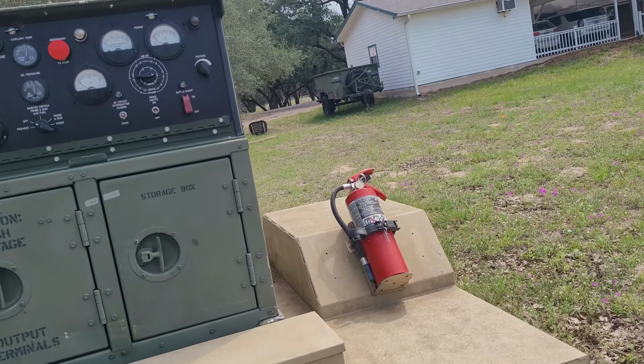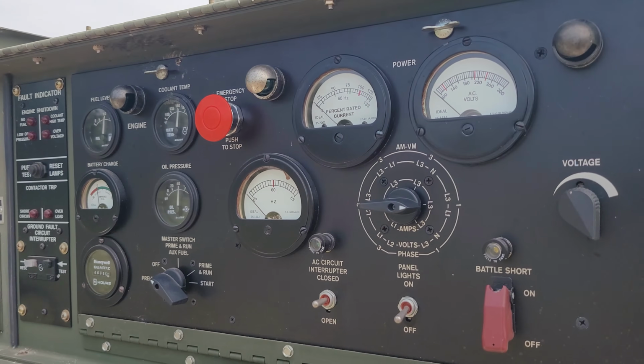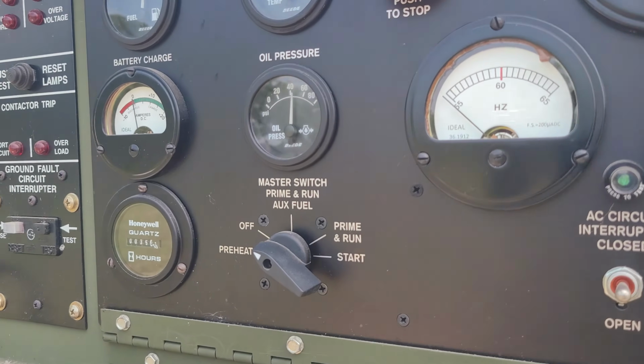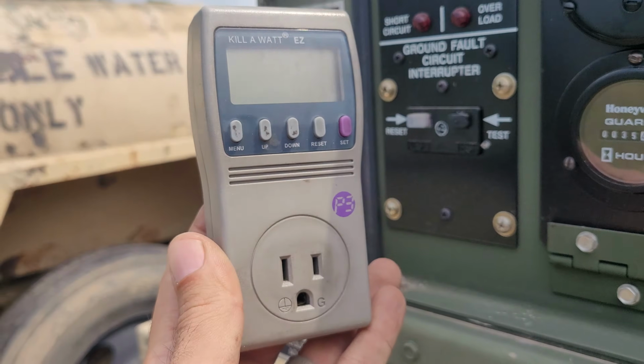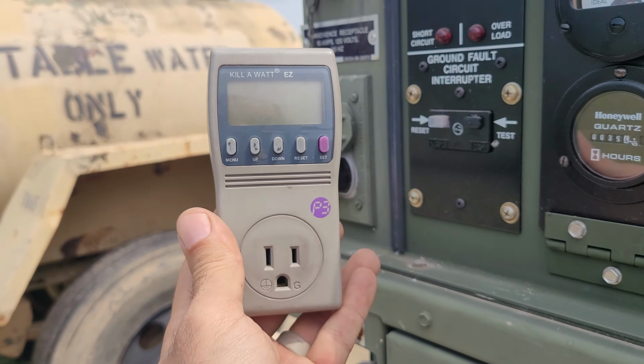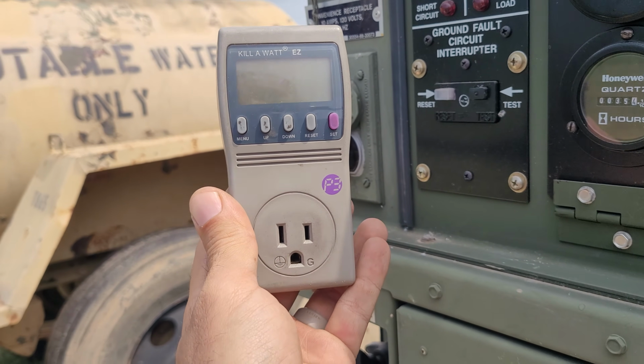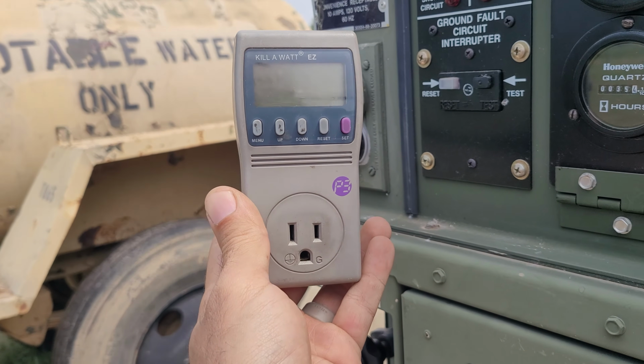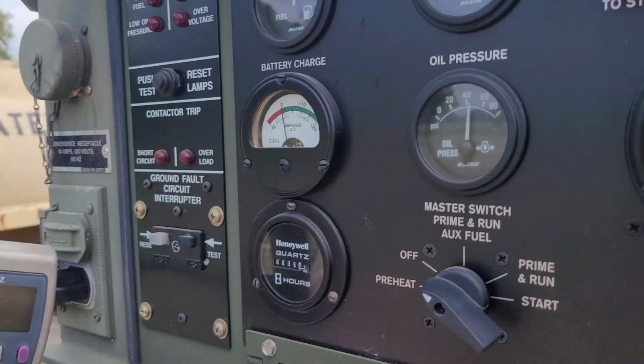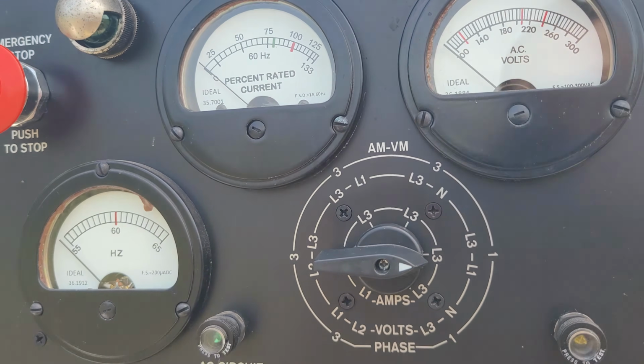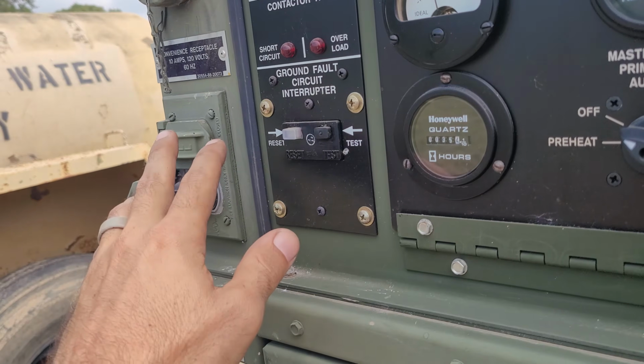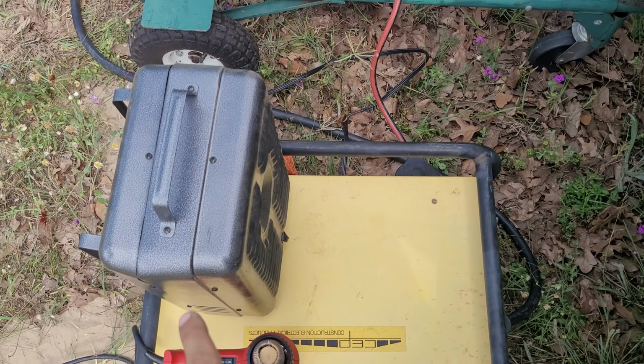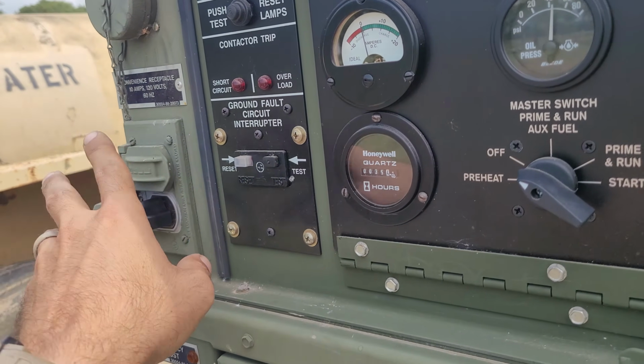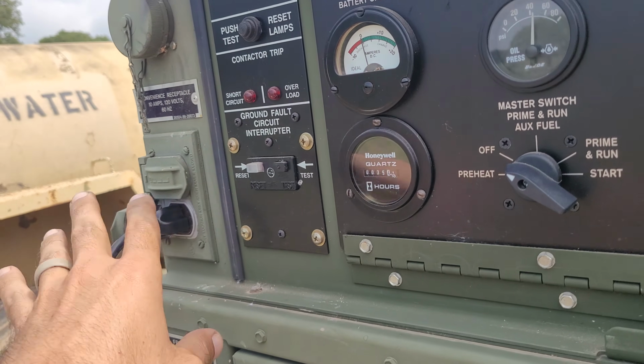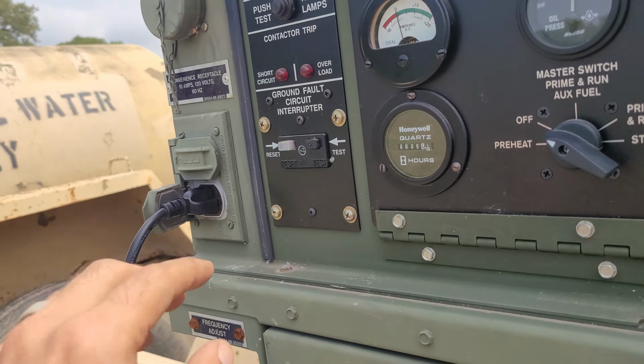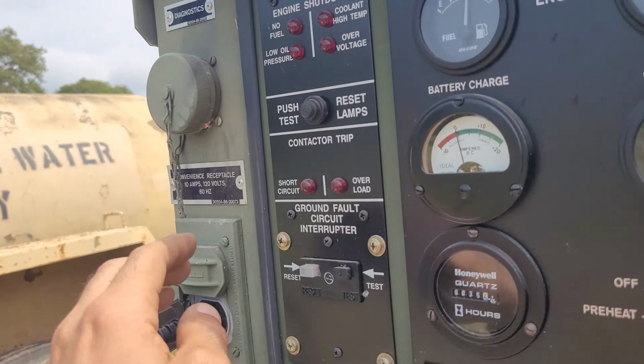Moving on to the generator. I'm assuming at this point you've already worked out all the mechanical issues and your fluids and everything are good. Having something like this that you can plug into the convenience outlet will give you a bunch of data, like your voltage and hertz, just to compare against your gauges here. It's good to have, but do not plug in stuff like your 110 heaters into this. It's meant for little lights and battery chargers as a convenience, that's why it's called a convenience receptacle.